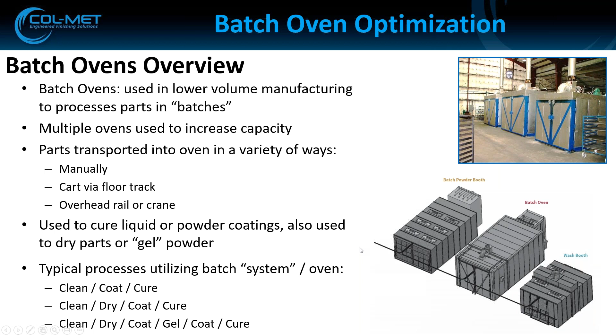When we talk about our BO, or standard batch oven, to identify how this differs from the VHD oven, the main difference is that we have the ductwork in the sidewalls of the oven, so we get more of a cross draft through this oven. This is a great solution for a wide variety of parts, and for more complex parts, the side ductwork with the H nozzle allows you to adjust and somewhat balance that airflow. One thing Col-Met always has is dedicated exhaust fans.